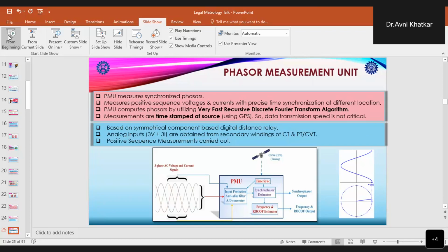And in the early 1980s, measurement systems started using the GPS to synchronize the sampling clocks, which offers a common time reference. The first experimental PMU was developed at Virginia Tech University in 1988, and Macrodyne was the first company to build a PMU in 1992. These PMUs measure synchronized phasors, the positive sequence voltages and currents, with time synchronization at all the different locations, and they compute these phasors by utilizing very fast recursive discrete Fourier transformation algorithms. And as I've already told, they are time stamped at the source, so data transmission speed is not critical, because all the measurements are time stamped at the source itself.